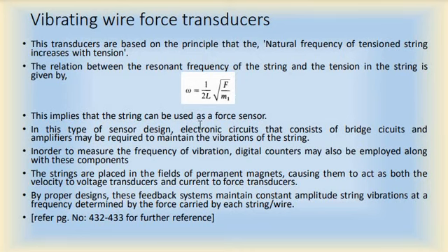In such cases, we have a vibrating string, and we need to keep this string continuously vibrating. For that, in some cases we may need a vibration exciting system that will act whenever the natural vibration ceases due to some delay in the tensioning force. So we require a vibration exciting system in order to keep the wire vibrating, to make up the frictional losses and to maintain the wire vibration at a fixed amplitude.